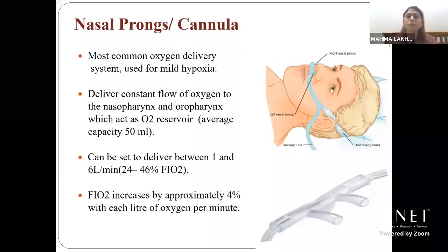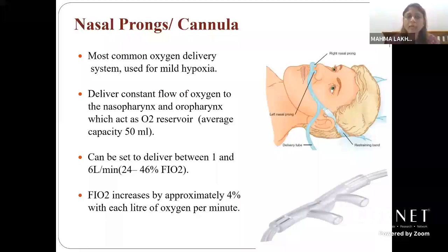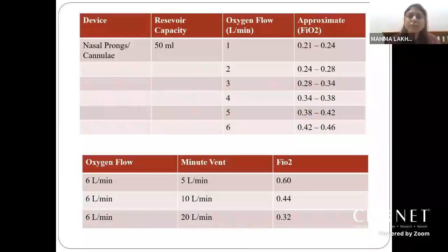First is the nasal prong. It is the most commonly used device in mild hypoxia. Here the reservoir is the nasopharynx and the oropharynx, which has a capacity of 50 ml. We can keep the flow from 1 to 6 liters per minute, and a maximum of 46% FiO2 can be delivered. This table shows that as we increase the flow rate from 1 to 6 liters per minute, with every 1 liter per minute increase in flow, the FiO2 will increase by approximately 4%. So the maximum that we can give with the nasal prong is at 6 liters per minute, that is 0.46 FiO2.